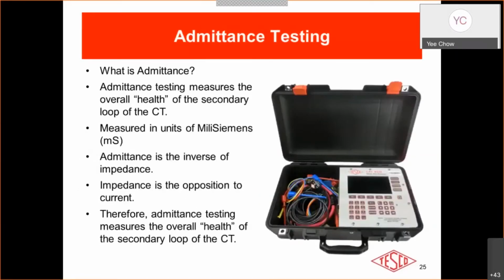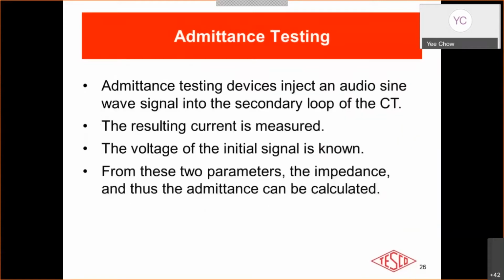Now we'll shift over to burden test or admittance testing. So first of all, what is admittance testing? You might or might not have heard this term used. Well, admittance testing measures the general overall health of the secondary loop of the CT. It's measured in millisiemens. Admittance is the inverse of impedance, and impedance is the opposition to current. So what we're doing is measuring how easily current can flow through the secondary of the CT and measuring the overall health of that secondary loop.